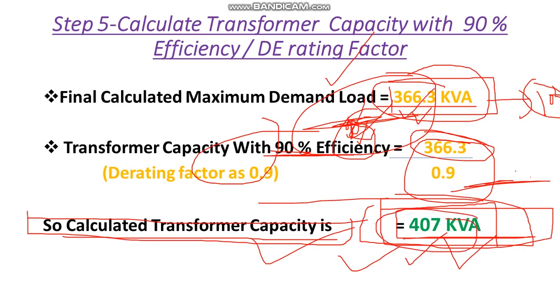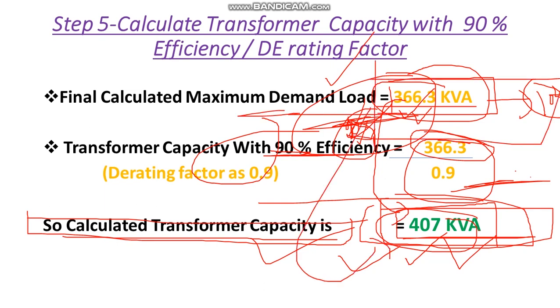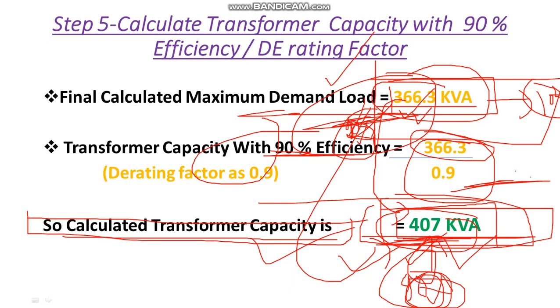Now if we connect the full maximum demand load of 366.3 kVA to this 407 kVA transformer, it means our transformer is operating at 90% load, which is the correct operating point. So 407 kVA is our calculated transformer size.